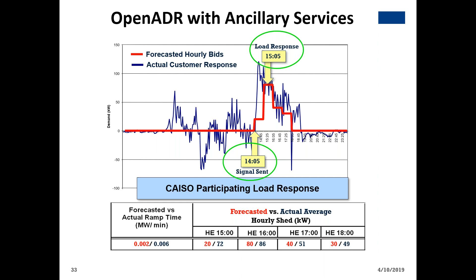This shows a CAISO forecasted hourly bid and the actual customer response. We were trying to see how fast we could get an electric load from a building to follow a signal from CAISO, looking at megawatts per minute—the red line is what we were trying to do, and the blue line is what we actually did. In general, we were able to get building loads to respond to the signals on a very fast time scale, using that 4-second telemetry with a slightly different architecture than we use for slower projects.